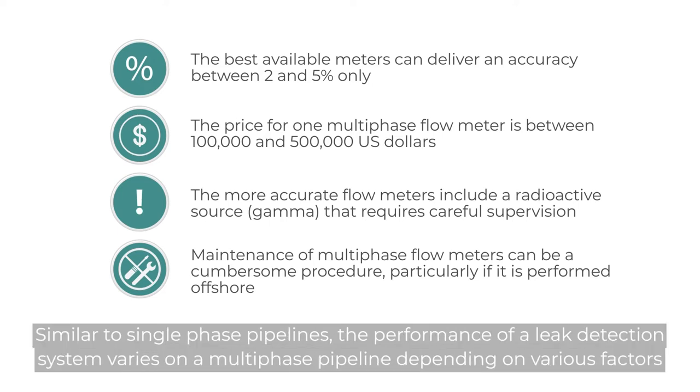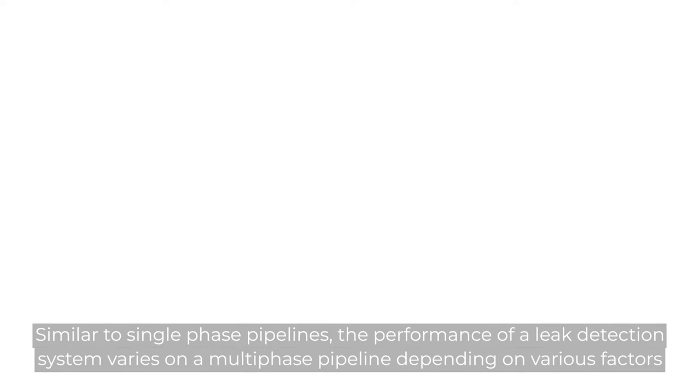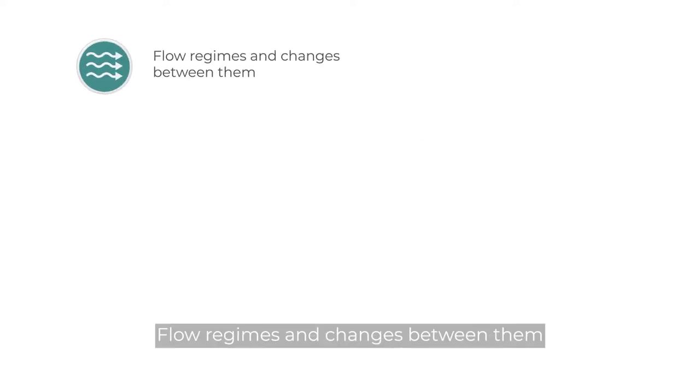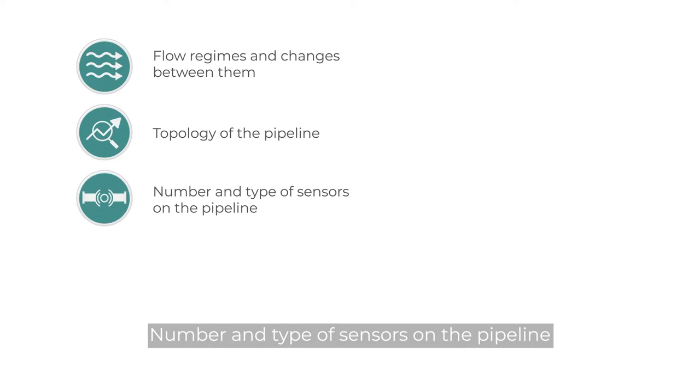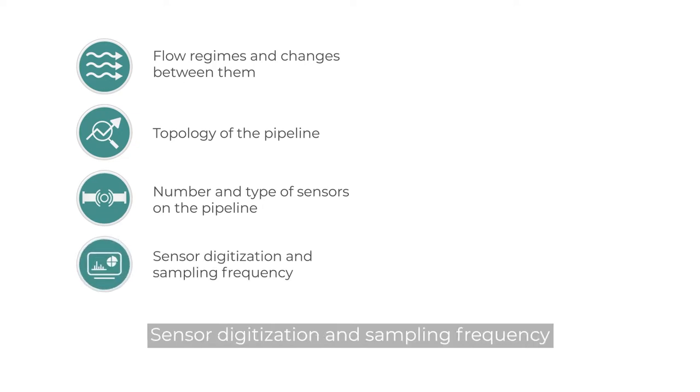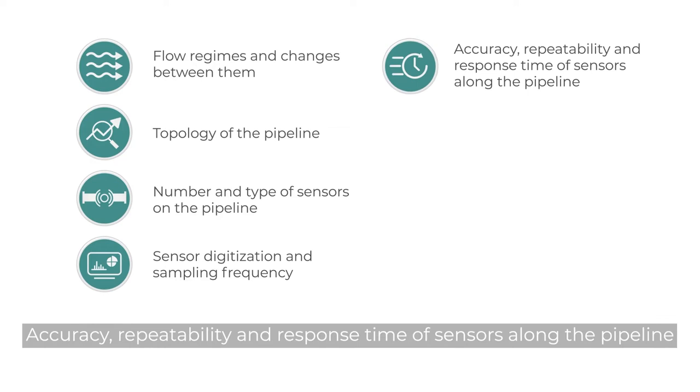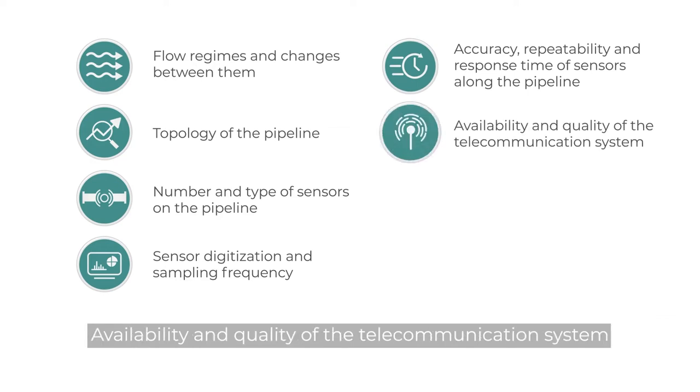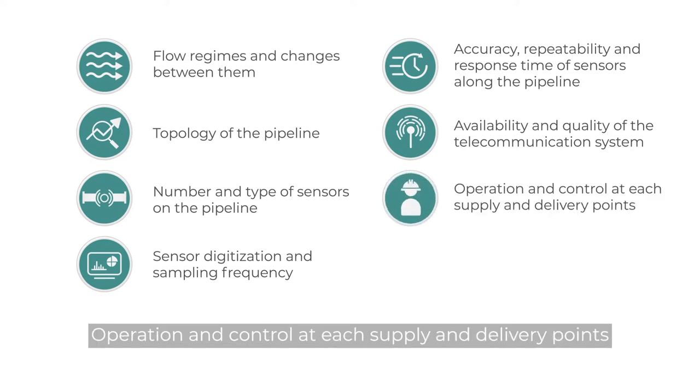Similar to single-phase pipelines, the performance of a leak detection system varies on a multi-phase pipeline depending on various factors: flow regimes and changes between them, topology of the pipeline, number and type of sensors, sensor digitization and sampling frequency, accuracy and repeatability and response time of sensors, availability and quality of the telecommunication system, and operation and control at each supply and delivery point.